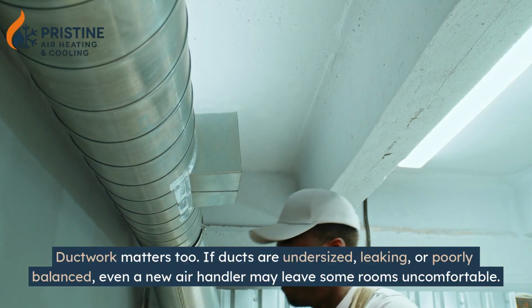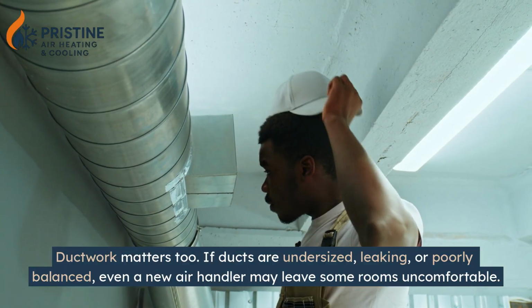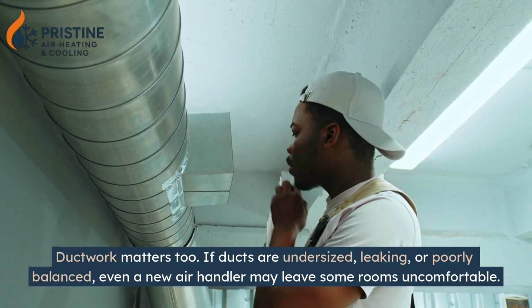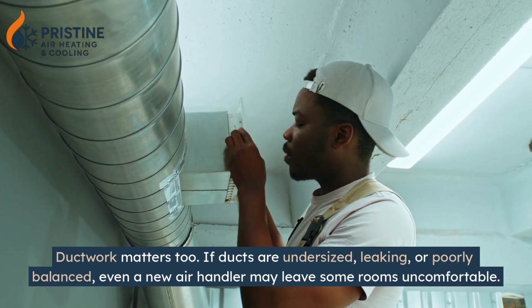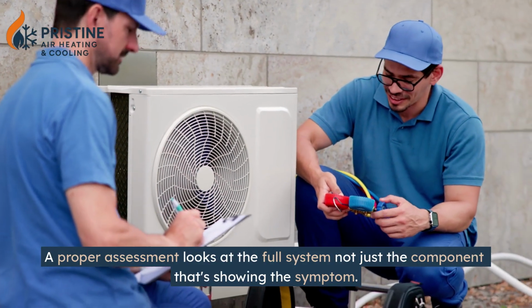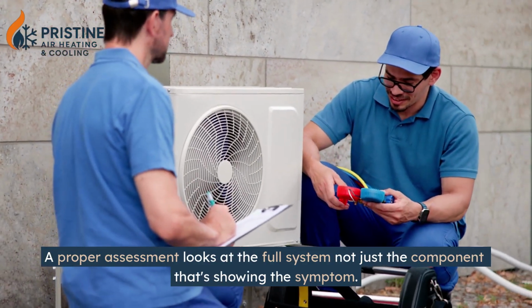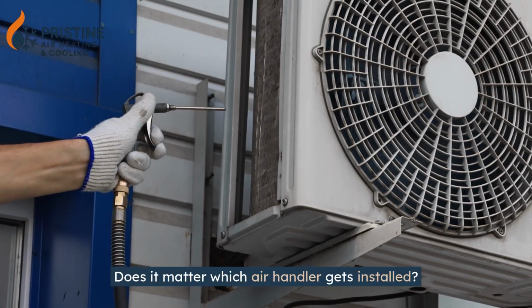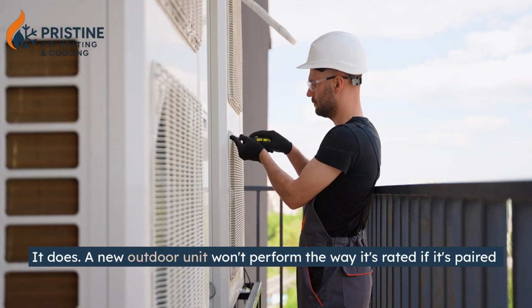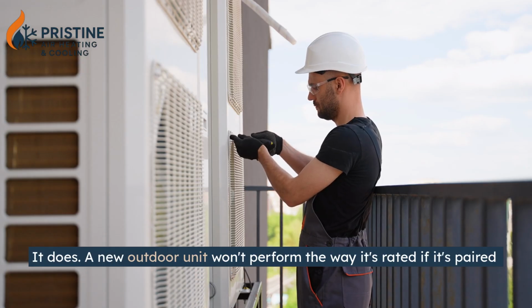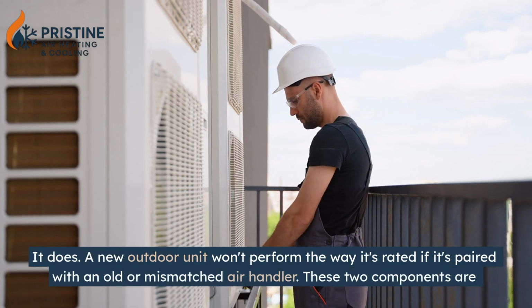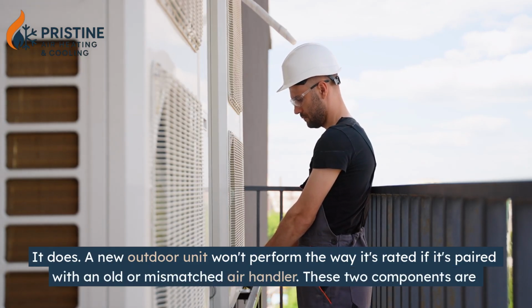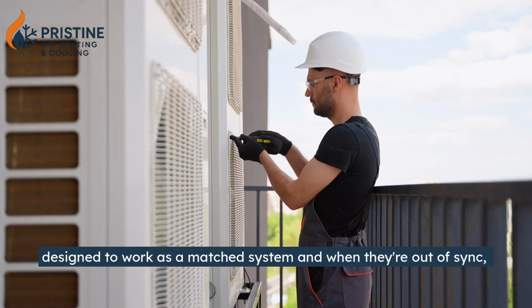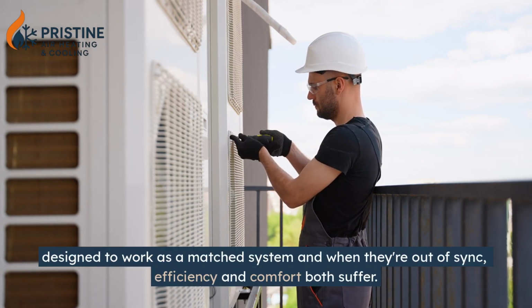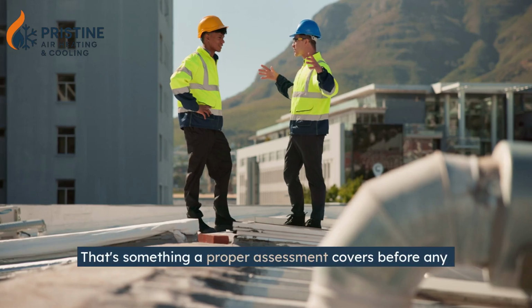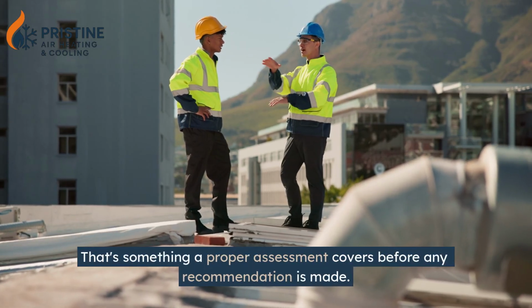Ductwork matters too. If ducts are undersized, leaking, or poorly balanced, even a new air handler may leave some rooms uncomfortable. A proper assessment looks at the full system, not just the component that's showing the symptom. Does it matter which air handler gets installed? It does. A new outdoor unit won't perform the way it's rated if it's paired with an old or mismatched air handler. These two components are designed to work as a matched system, and when they're out of sync, efficiency and comfort both suffer. That's something a proper assessment covers before any recommendation is made.